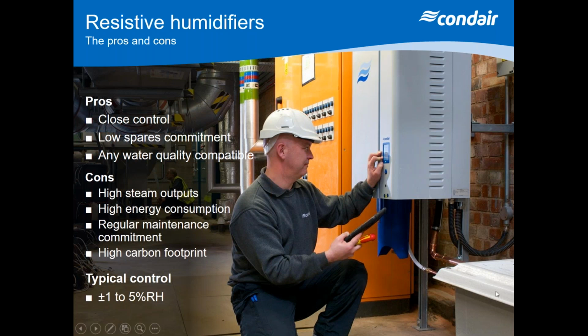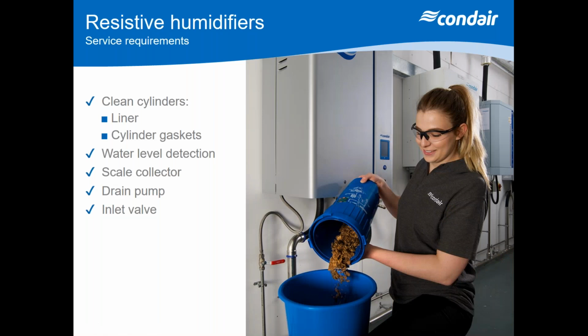In terms of maintenance, you're going to find that you're going to have to clean the cylinders out. There'll be an internal liner in most cases with these units, which you need to clean out and replace every so often. And the liner is there to prevent you getting scale on the insides of the tanks. The neoprene gaskets that seal the top half of the cylinder and the bottom half would need to be replaced every year, we recommend, because they become depressed and they don't reseal correctly. So it's always worth just changing the gaskets on those cylinders. And the most important part of a resistive humidifier is the water level detection. And that could be a variable capacitance, if it's an effect sensor, which is some of those units that are out there, or it could be a float, a reed switch.